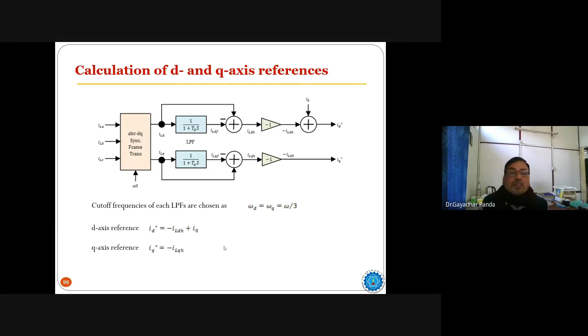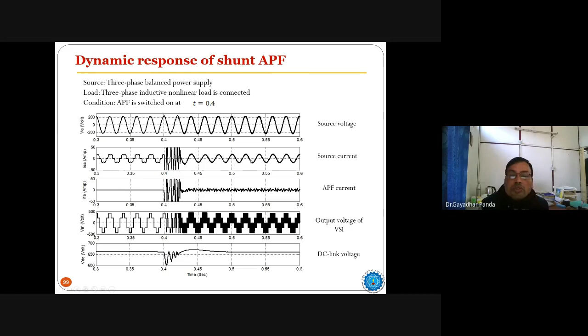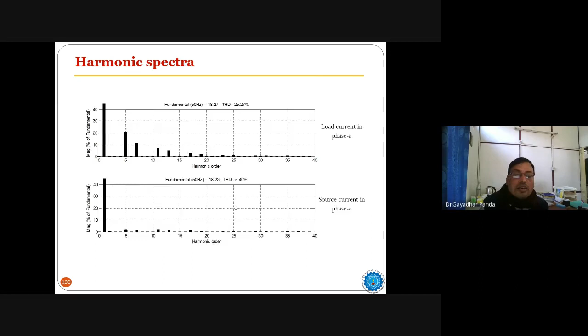Here you can see the different test cases we have taken for this active power filter, and we have checked how the harmonics are reduced by using the active power filter. Here you see that without the active power filter, your source current is distorted in nature. And after this, we are connecting an active power filter, where the source current is coming almost sinusoidal. Voltage is sinusoidal, there is no problem, but because of the nonlinear load, the load current is non-sinusoidal. Once you connect the active power filter, the compensating current will be produced, which will eliminate the harmonics. This is almost the desired value, because the THD is within the limit, that is around 5.4. Still, it depends on the control algorithm also.